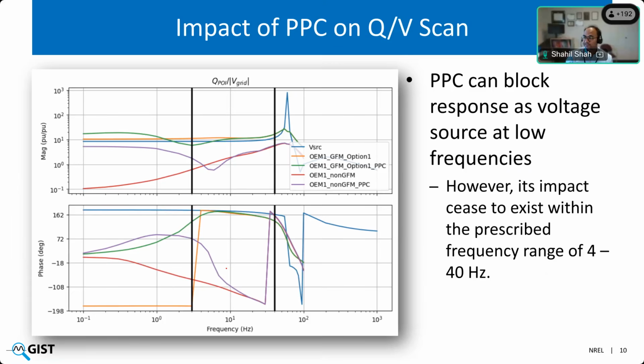Deepak, can you go through this slide on impact of PPC? Yeah. So the idea here is also to showcase that you can look at this from an inverter or element level perspective versus a plant level perspective, because there's a difference between looking at the POI bus versus the inverter terminals. The role of the PPC usually comes into play more in the slower behavior, closer to a steady state response, because it's a much slower control. So what we're showing here is that irrespective of whether the PPC exists or not, we see the voltage source property coming out more in that 4 to 40 hertz range.